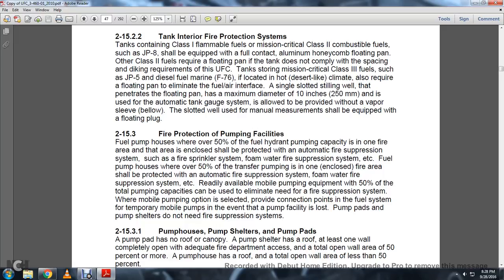2-15.3 Fire Protection Pumping Facilities. Fuel pump houses where 50% of the fuel hydrant pumping capacity is in one fire area, and that area is enclosed, should be protected with an automatic fire suppression system, such as a fire sprinkler system, foam water fire suppression system, etc. Fuel pump houses with over 50% of the transfer pumps in one enclosed fire area should be protected with an automatic fire suppression system. Foam water fire suppression systems readily available with mobile pumping equipment with 50% of the total pumping capacity can be used to eliminate the need for the fire suppression system when the mobile pumping option is selected, to provide connection points in the fueling system for temporary mobile pumps in the event that the pump facility is lost.